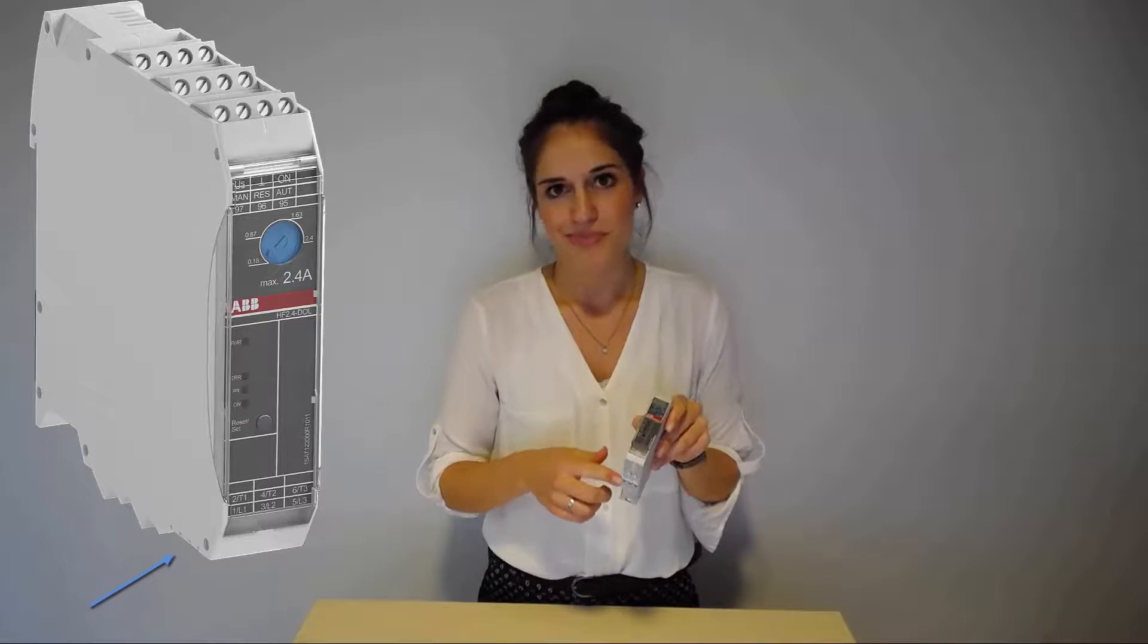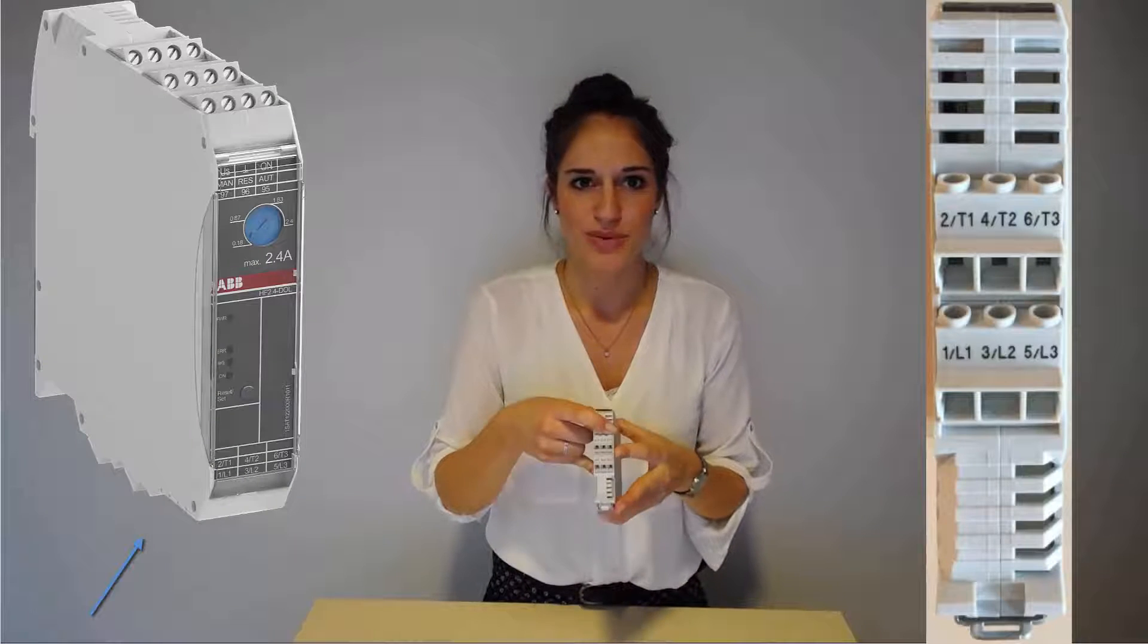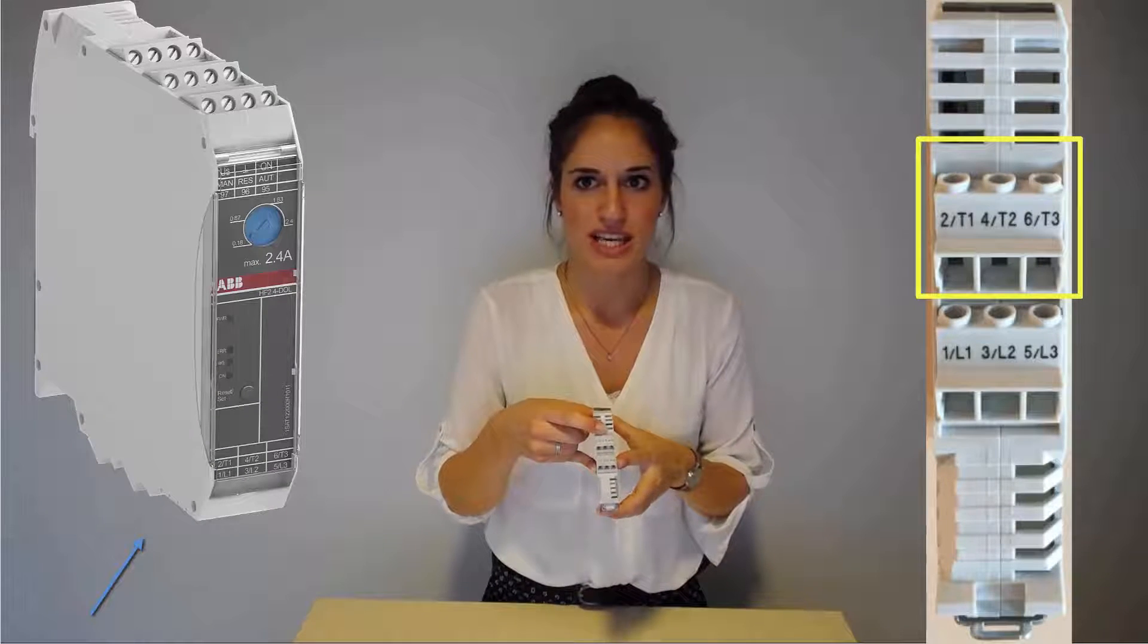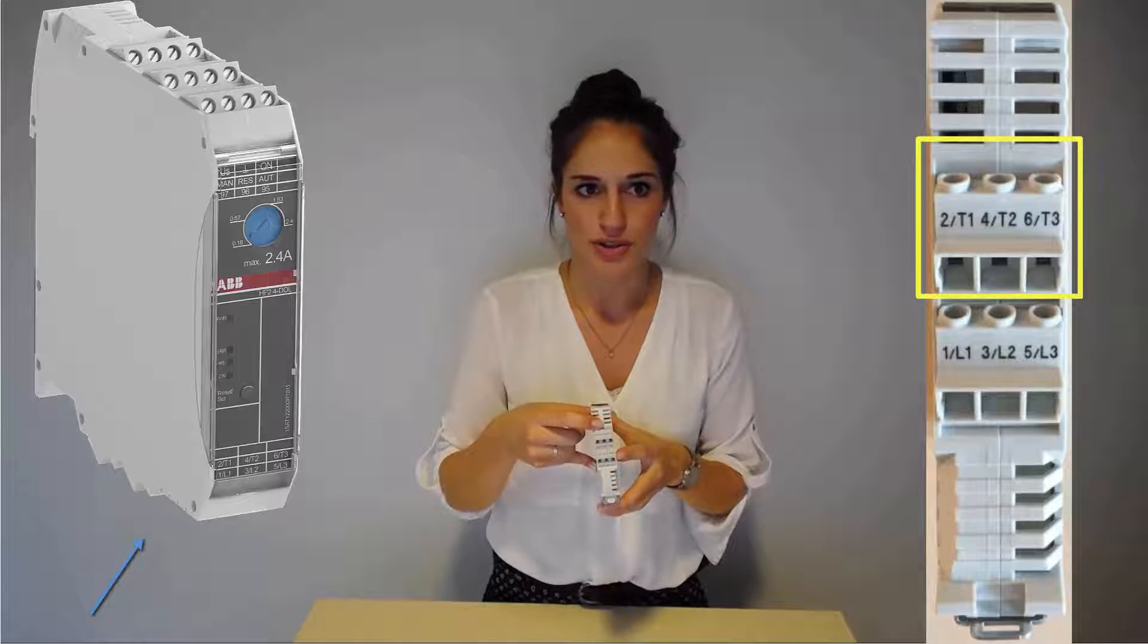Motor control terminals can be found on the top side of each device, whereas the three-phase power supply for the motor is realized on the bottom. Terminals T1, T2 and T3 are the output voltage terminals. They have to be connected with the motor.